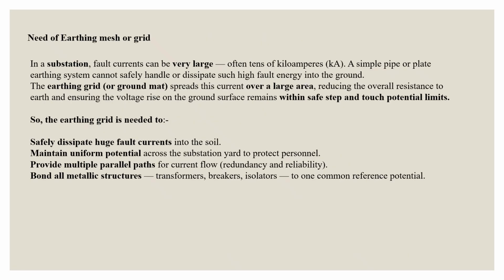So why is there a need for an earthing mesh or earthing grid? In a substation, fault currents can be very large, often tens of kiloamperes. A simple pipe or plate earthing system cannot safely handle or dissipate such a high amount of current into the ground. The earthing grid or earthing mat spreads this current over a large area, reducing the overall resistance to earth and ensuring the voltage rise on the ground surface remains within the safe step and touch potential limits.